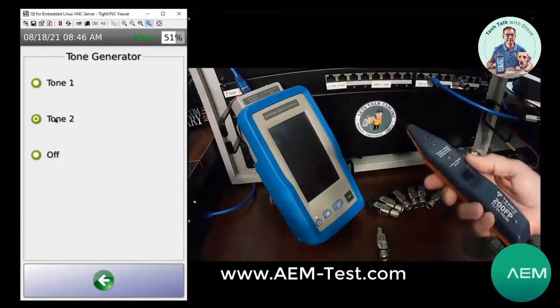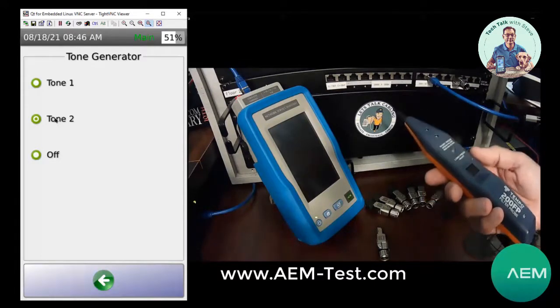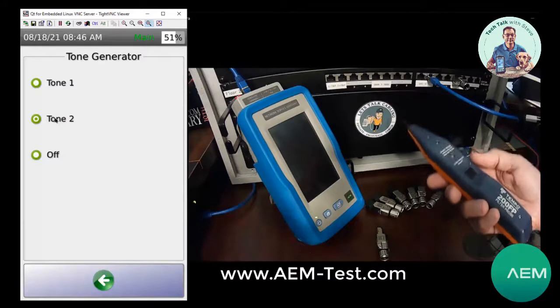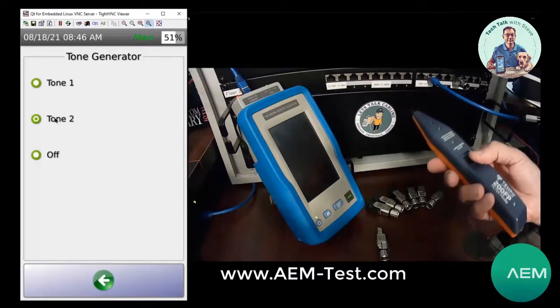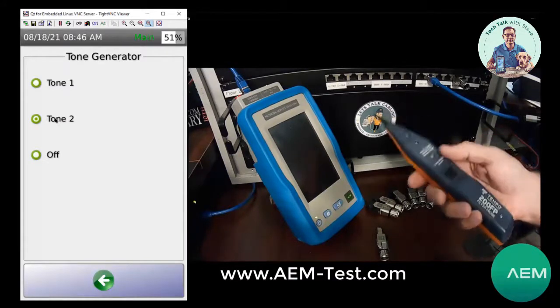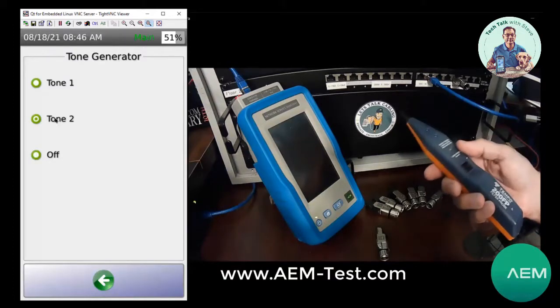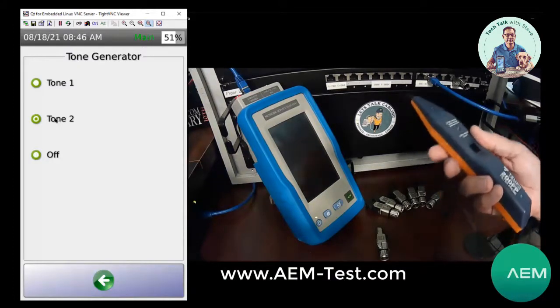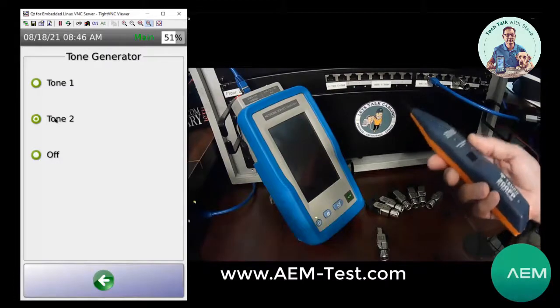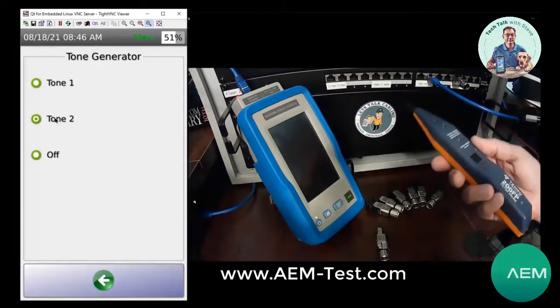The signal strength indicator is useful for a couple of things. If you get in an environment with a lot of equipment, a lot of noise in the background, and you can't really hear the tone, you can watch that light and see it light up, and you'll know you're on the tone. More importantly, anytime you're doing a tone and probe operation, there's always the chance of bleed over between ports on a panel or between cables in a bundle.